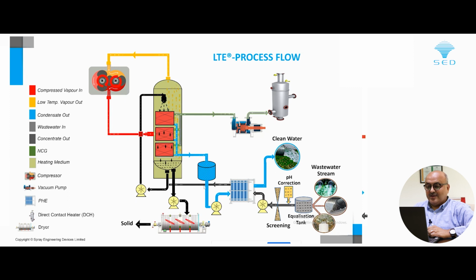First we create a vacuum. Actually water boils at 100 degrees. This is a universal fact, but we do this whole evaporation at 60 degrees at a negative pressure of 20 kPa. We create the vacuum inside the whole of the system, and then feed the wastewater at 60 degrees, and then get recirculation by the feed directly into the evaporator. And these red boxes are basically the evaporator cum condenser, and in this low pressure and low temperature, vapor from the bottom of the evaporator goes up.